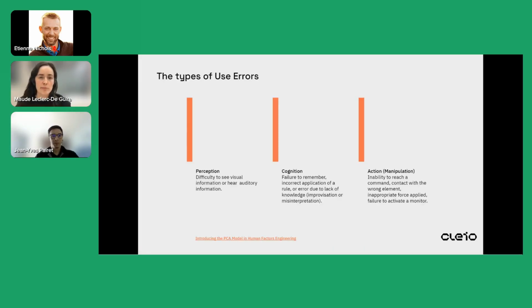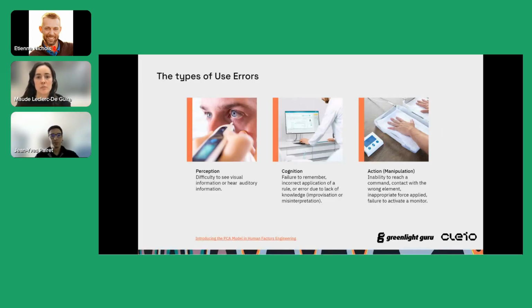There are three types or sources of use errors. It can come from the perception, so difficulty to see a visual indicator, for instance. The cognition, failure to remember, or the user is improvising to complete the task. Or the action, manipulation, so the inability to reach a command because it's too high. So it is important to remember that a single use error may include more than one type or source. This way of analyzing the risk of use is called the PCA technique, which stands for perception, cognition, and action. It is a very useful tool to give some depth to your task analysis and your URRA as well.